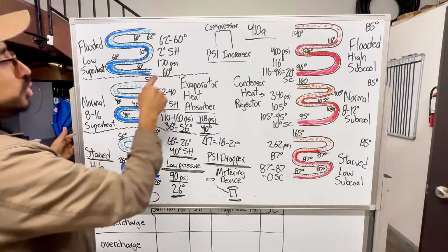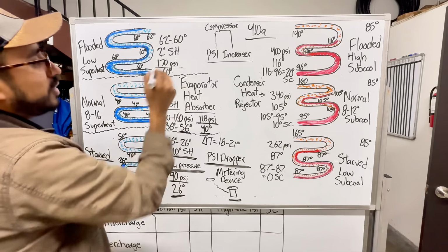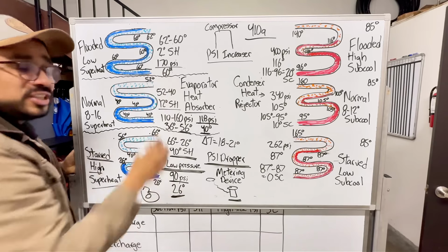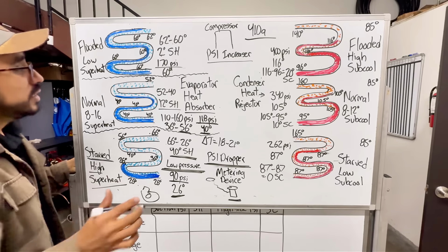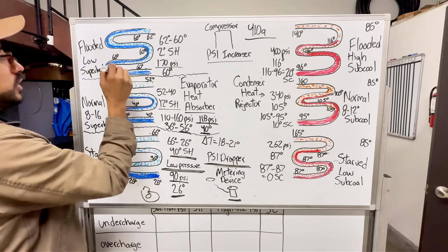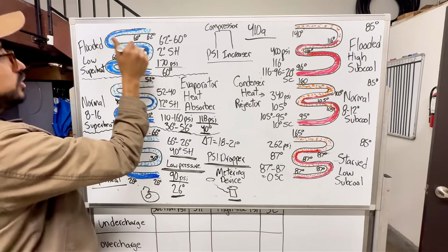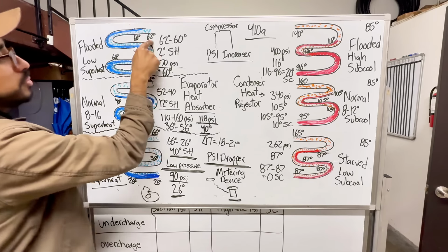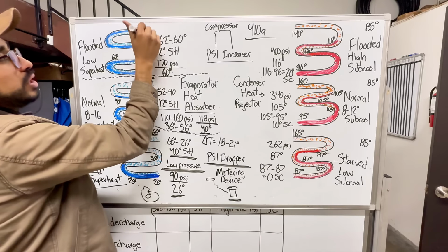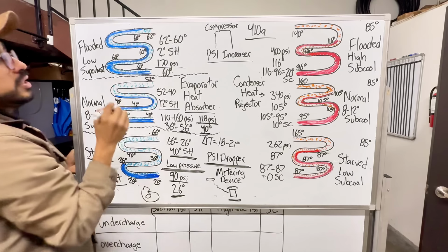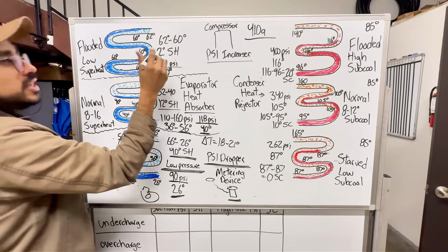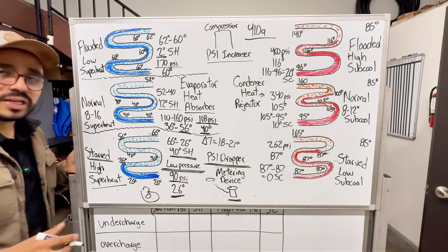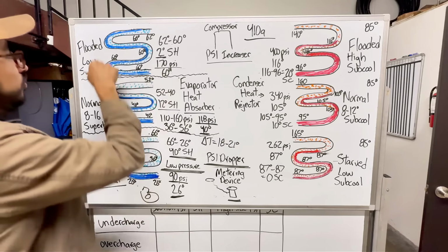So when you connect your gauge, 170 psi, that's a 60-degree evaporator temperature. So you're not going to do great cooling. But when you get your superheat, 60, 60, right? As long as it's saturated, 60, 60, 60. And boom, it only boiled off, let's say this part. So once you get your superheat, 62 minus 60, that's a 2-degree superheat. That's too low. That's a flooded evaporator.